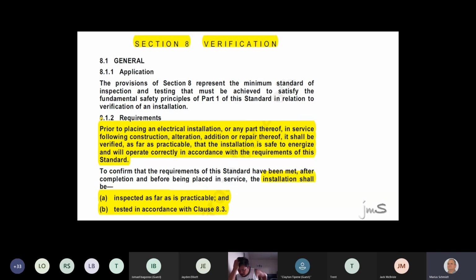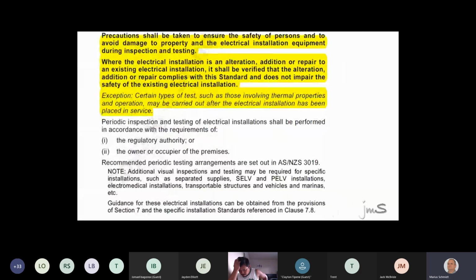Testing is critical because we don't want to liven installations. Right, it says at the top of AS/NZS 3000, precautions shall be taken when we do testing. Now, Act 82 states very clearly, you can liven an installation for testing purposes. You guys got it? Act 82. Act 82 also states you can liven it from any supply, from a temporary building supply up to a generator, or at the end from the real supply. You guys okay with that?